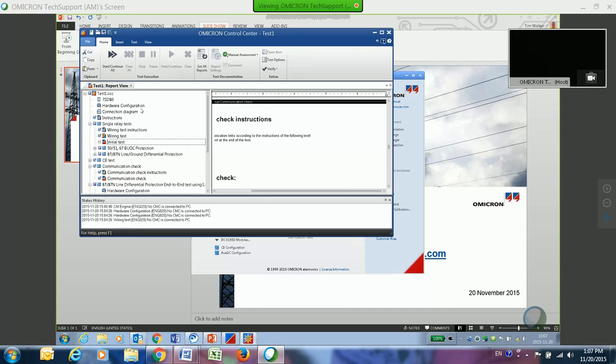So it means if I just want to do a zone reaches test, I can select all zones as tripping zones, select the search test, and do my zone reaches. Yes, exactly. It would go through and check those for you.